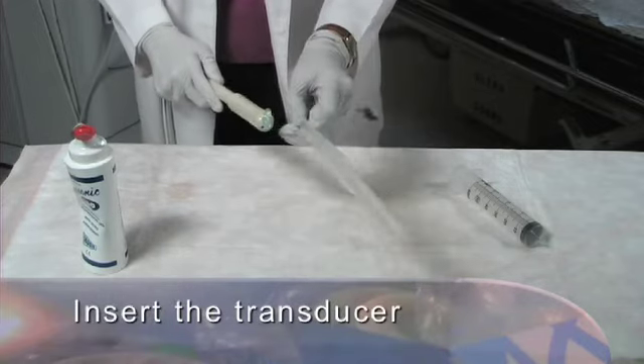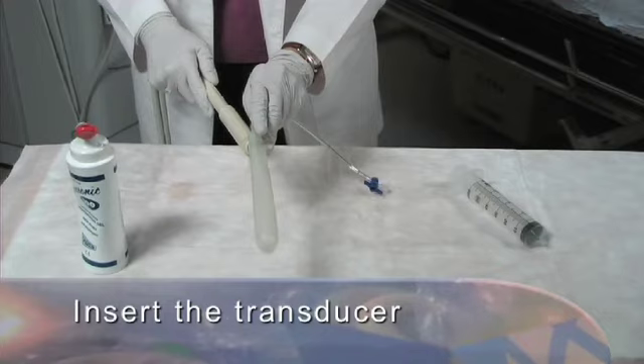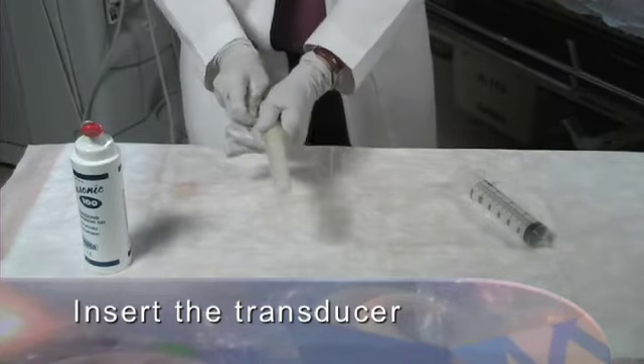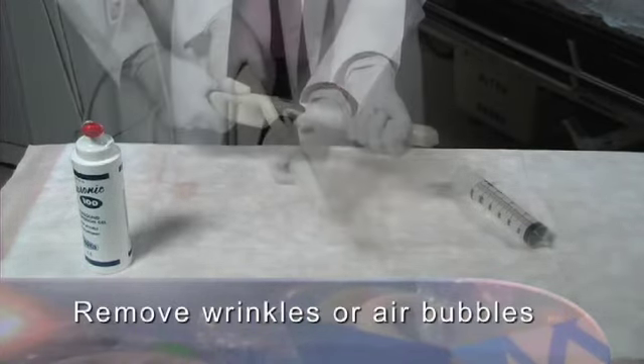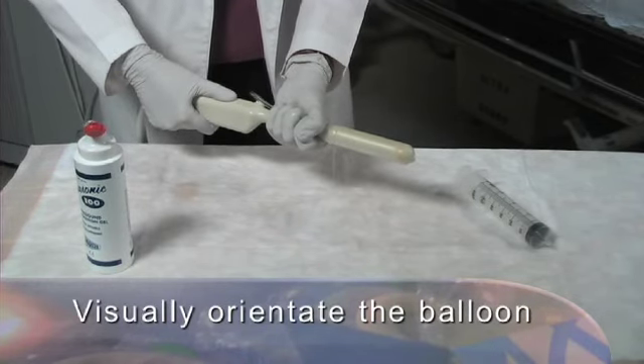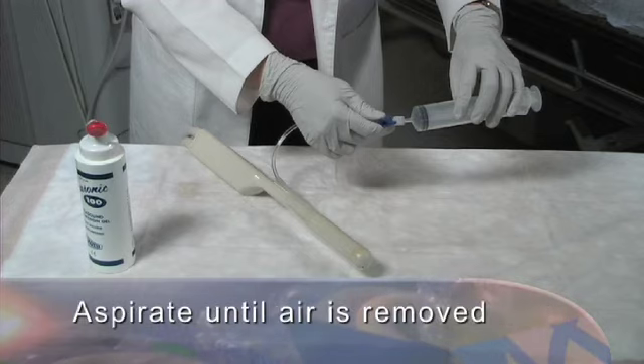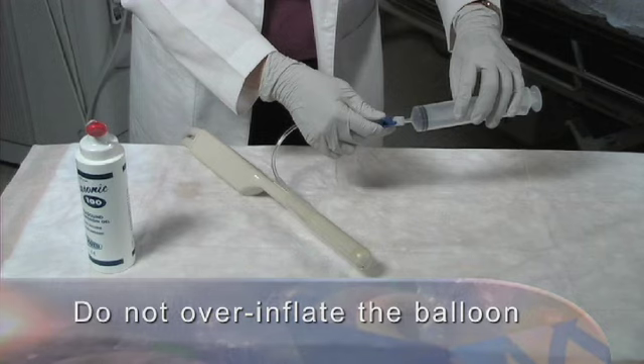Inserting the transducer into the balloon with the fill tube oriented in top center of the transducer. Pull the balloon tightly over the transducer face, removing wrinkles or air bubbles. Visually orientate the balloon so lateral seams are a symmetrical distance from the longitudinal array. Use a 30 cc syringe to fill the balloon with saline solution. Aspirate until air is removed. Do not over inflate the balloon.